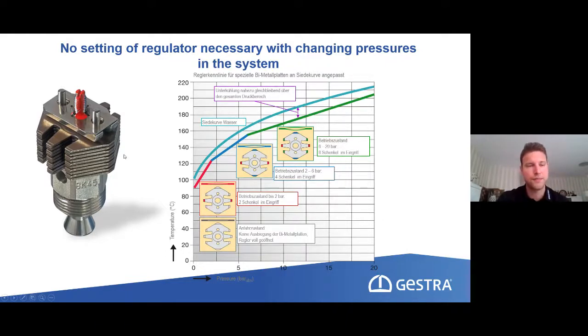Unfortunately, bimetallic controllers usually have a linear opening characteristic. This was the reason why we could only use bimetallic steam traps at high pressures. When we have more than 10 bar, then we could only use bimetallic. But we also want to have the advantages of a BK at lower pressures, which we have here. So we had to do something to realize a bending of the opening characteristic, like the saturated steam curve does. And we did this with this very specific shape of the stainless steel plates that we see here. With this design, we have only 2 connection points at low pressures, so only this one and the one on the opposite.